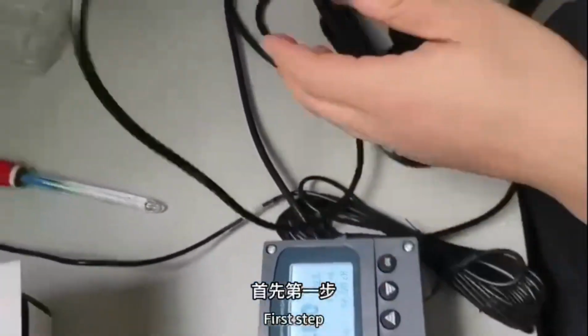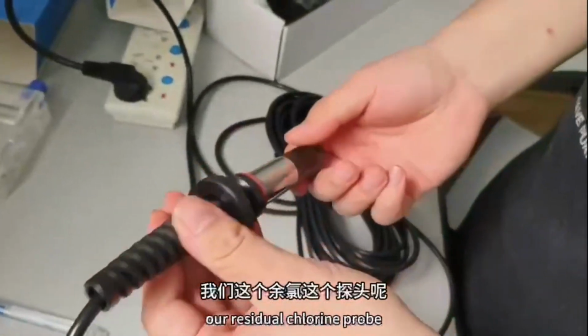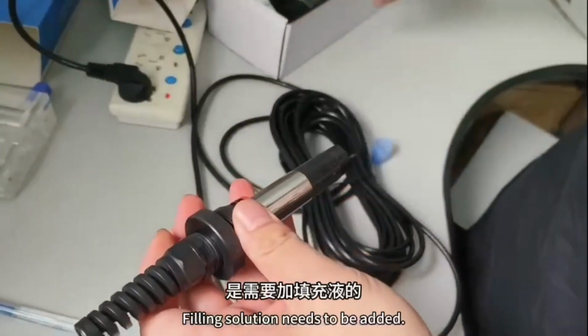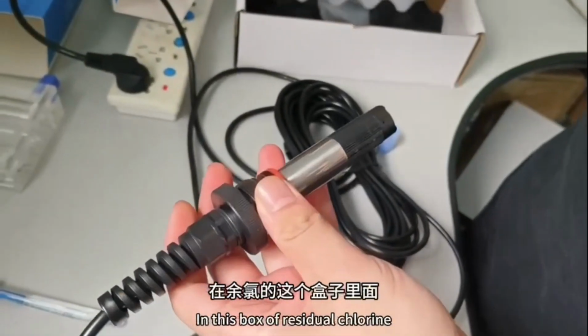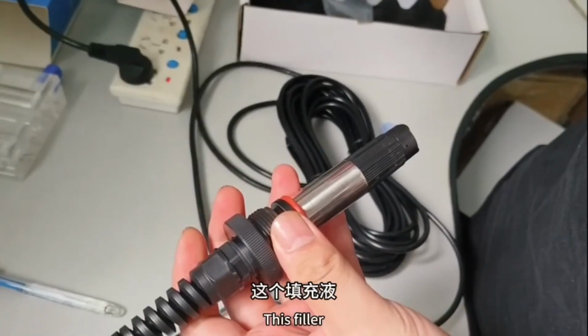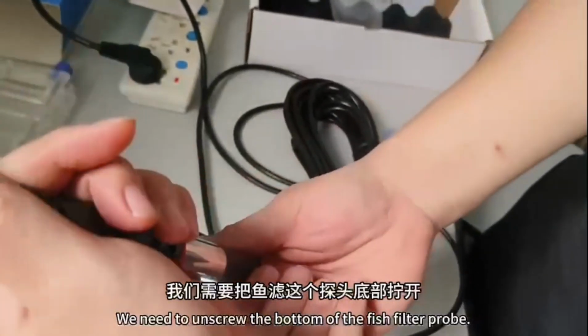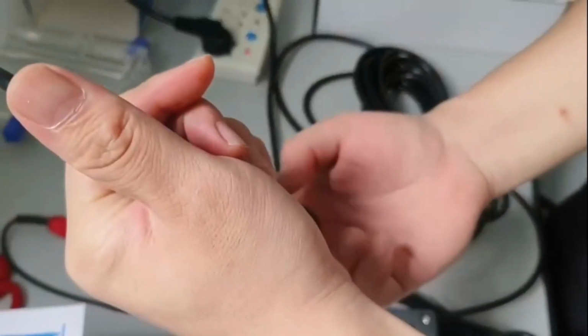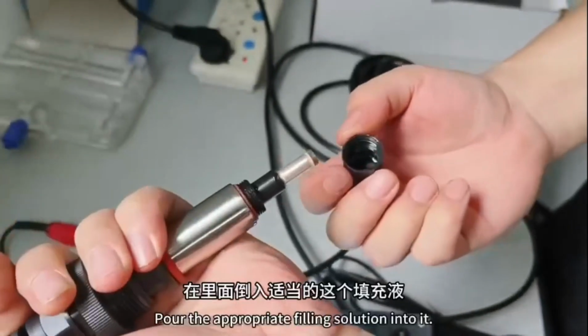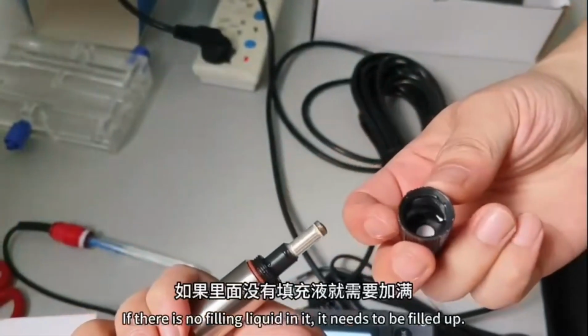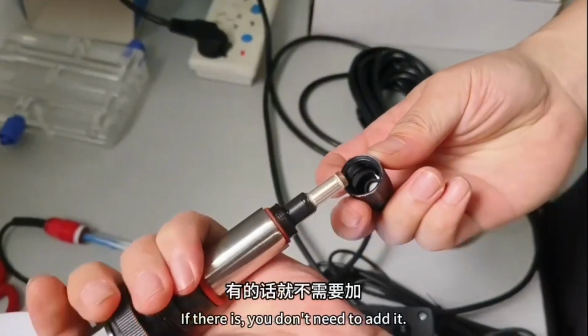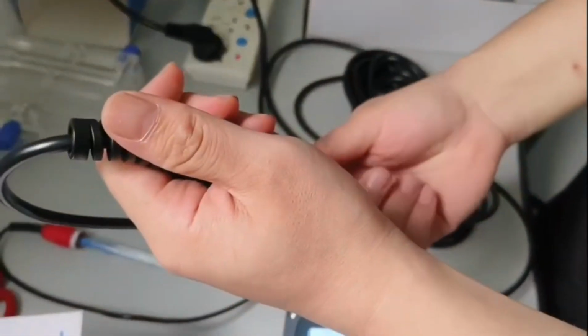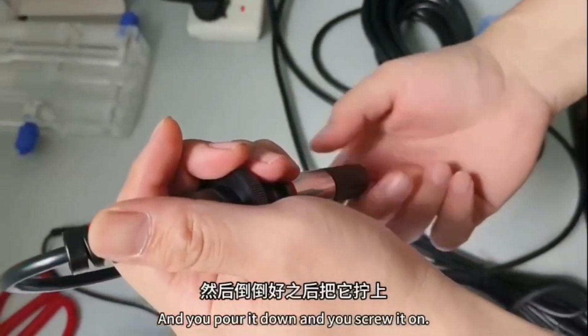First of all, the first step, the residual chlorine probe needs to be filled with fluid. Inside the box for residual chlorine, there is an electrolyte. This filling liquid we need to unscrew. At the bottom of the probe, pour the appropriate filling liquid into it. If there is no filling liquid, it needs to be filled. If there is, no need to add. Pour the filling liquid and screw it on.